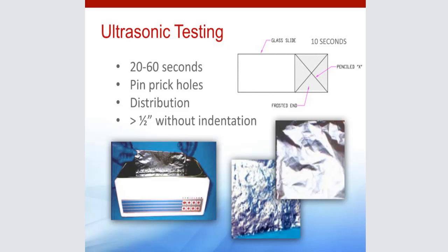The other thing to look at, one of the newer methods: there are ultrasonic disposable tests that are available from a number of manufacturers right now. Those can also be used. But I know in Canada, they are using the glass slide. What they're recommending is that it's frosted on one end, and you dip the glass slide in water to get it moist. Then you take a number 2 graphite pencil and you mark an X on the frosted end of the slide, and then you dip the frosted end into the ultrasonic solution. You run it for about 10 seconds, and all of that graphite should in fact be removed at the end of that cycle.